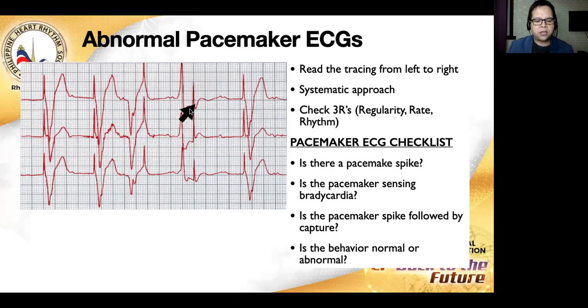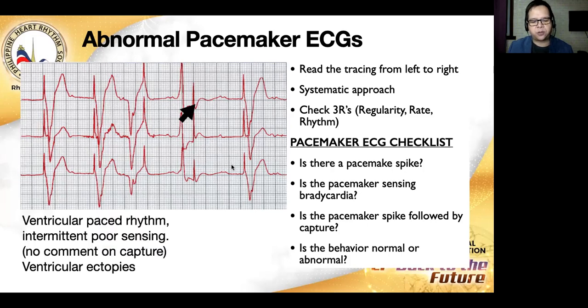Now, can you comment on the capture? There's no capture here because it falls during the refractory period. So the pacemaker is not sensing these intrinsic beats and is pacing inappropriately. So this one is ventricular paced rhythm with intermittent poor sensing with intrinsic ventricular ectopies.